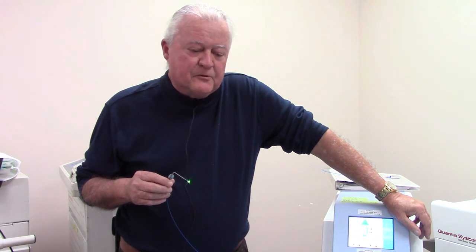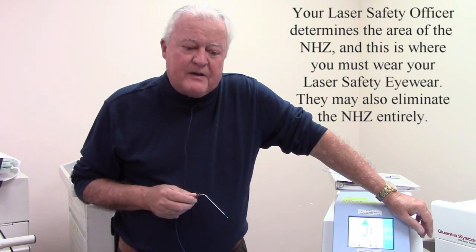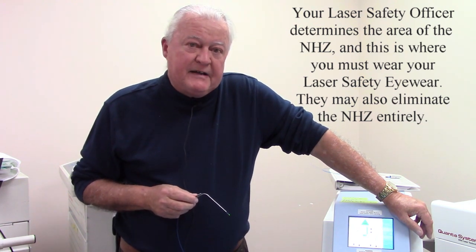How far away was I? That far. I'm not going to go to two inches and try the same thing. But the point is: if you're working with a Holmium YAG laser, it really is fairly safe. You've got to be very close to someone to burn them. The real risk is breaking a fiber in a surgical field where there are paper drapes and setting a fire — that is a problem. But this concern about people having eye problems around the room is just nonsense. You could make the case that if you're going to be right there close up, you need to wear the glasses — you can do that if you want to be ultra conservative. But really, it's just a few inches. The laser safety officer is allowed to use their judgment and equivalent assessments in order to set up nominal hazard zones. And the ANSI standards say that if you're doing an endoscopic case, you can elect not to use safety glasses anyway. So you decide for yourself. I just wanted to show you here what the real risks are.